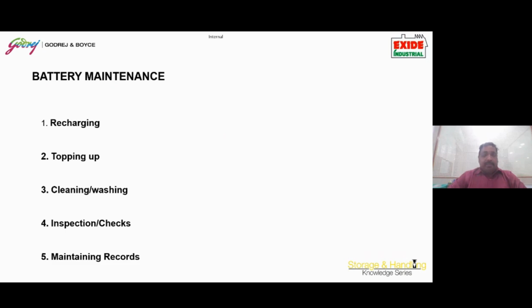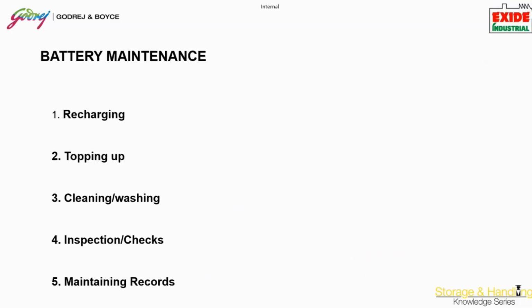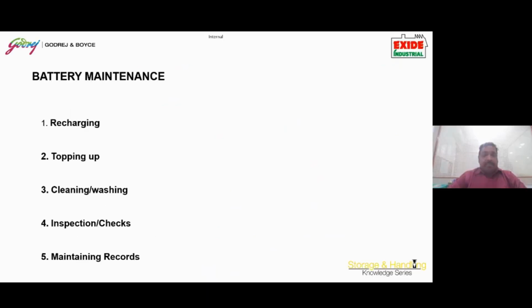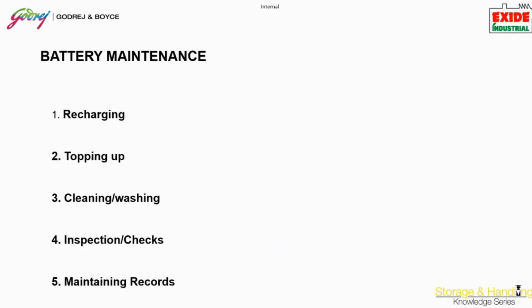Cleaning and washing is very important because during top up, or during the course of forklift operation, with load, without load, on any rough surface, if the top up has been done and water levels are at the top, there is likely to be spillage. Since this spillage is of electrolyte, when it dries, a current path will form which will cause leakage current. So cleaning and washing at regular intervals are important, and testing of the leakage current is also important.